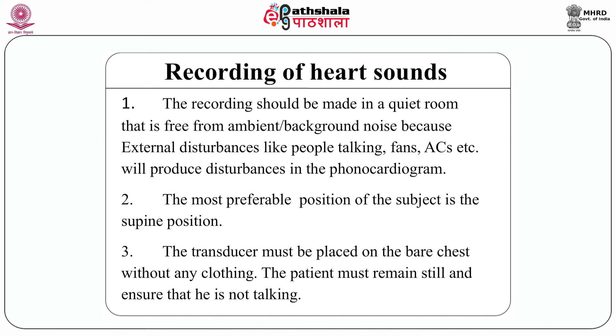Third, the transducer must be placed on the bare chest without any clothing. The patient must remain still and ensure that he is not talking. Fourth, the transducer should be in full contact with the chest wall with gentle pressing. Fifth, no undue pressure should be given on the transducer on the chest wall, because the heart sound may get distorted. We should also see that the hair on the chest wall should be shaved or plastered down before applying the transducer so as to prevent any artifact.